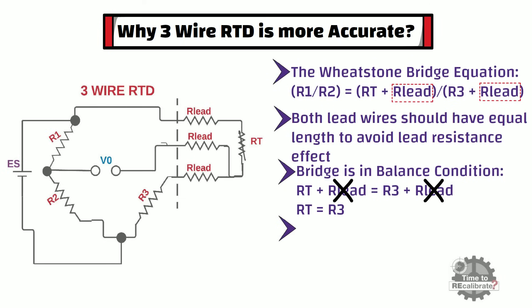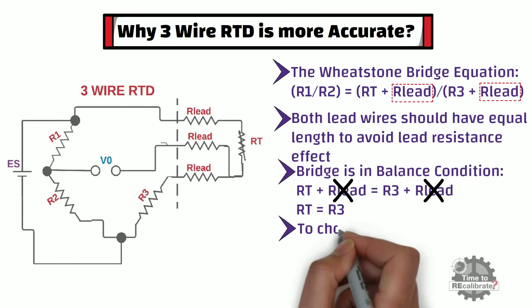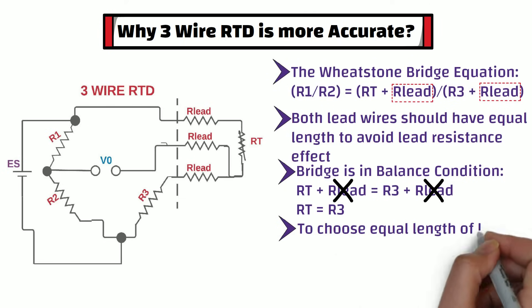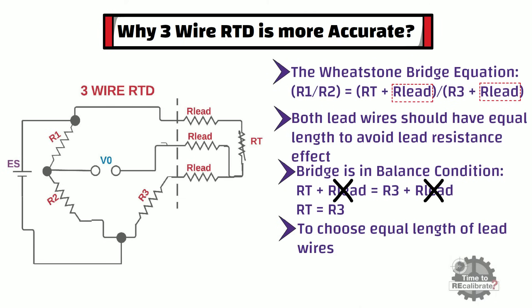However, as I said earlier, great care needs to be taken to choose equal lengths of lead wires. In other words, if you do not choose equal length lead wires, a temperature measurement error will occur.